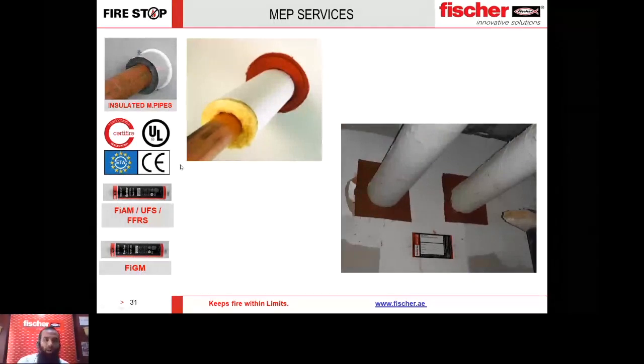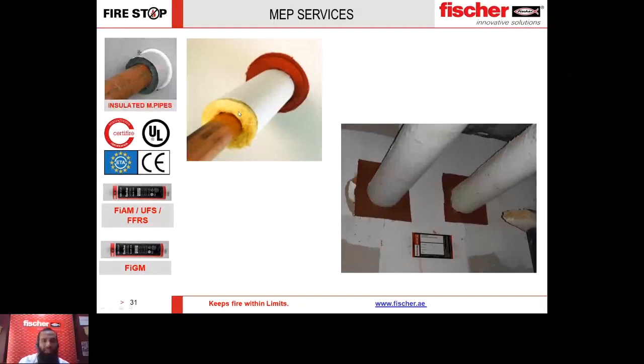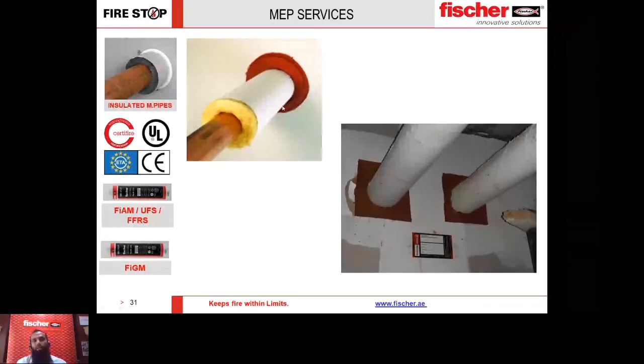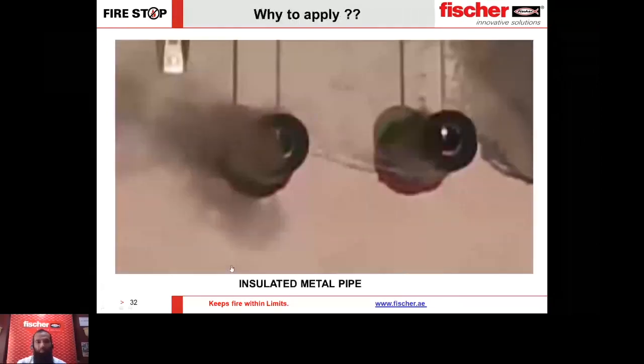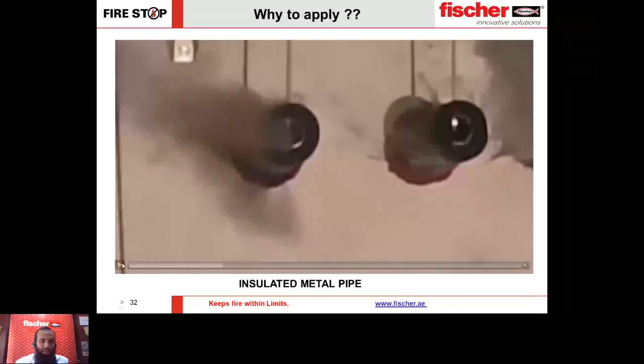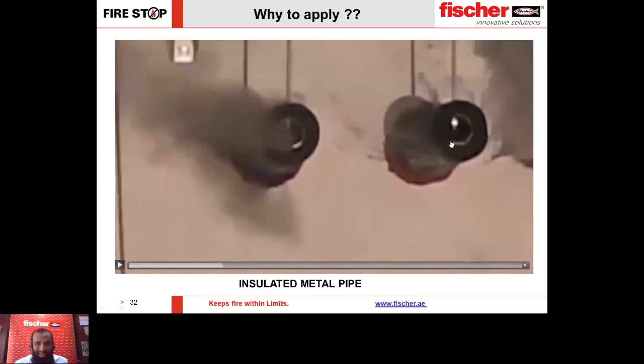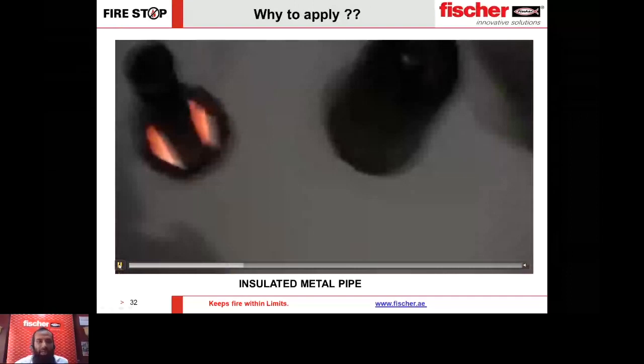For insulated metallic pipes, we have tested systems listed to UL and also to British standards. A very important parameter in this application is the insulation thickness and insulation type. The proposed products are FIAM UFS and FIGM. Note that two identical-looking applications can perform very differently — just because the type of insulation changes, the insulation can burn away leaving a huge gap. Please ensure when you ask us for a solution you mention all parameters required.